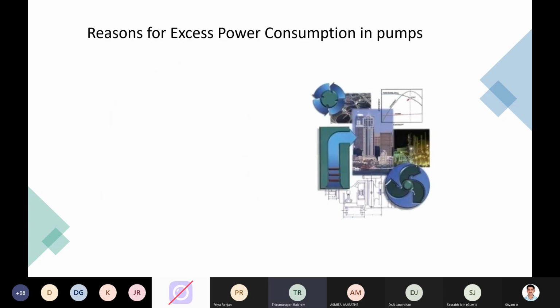Okay, so some factors, like when you find there is an inefficient pump, obviously that is a tag to your power consumption. So now what would be the reason for excess power consumption? For example, you have a pump and it is 11 kilowatt, and you see the energy consumption is close to 10 kilowatt. So now you can find out what would be the avenue you can save power in that particular product. Is there any viability to save power? And if it is some extra factors we are able to overcome, definitely we are able to arrive at that.